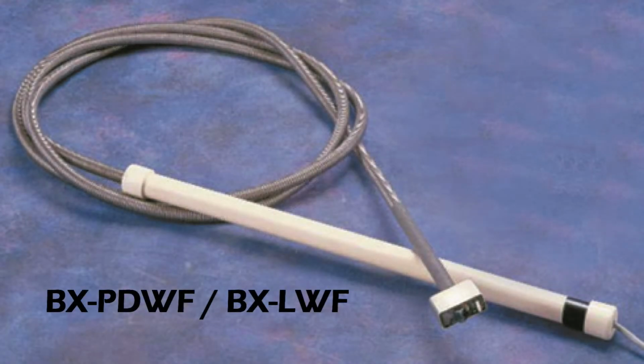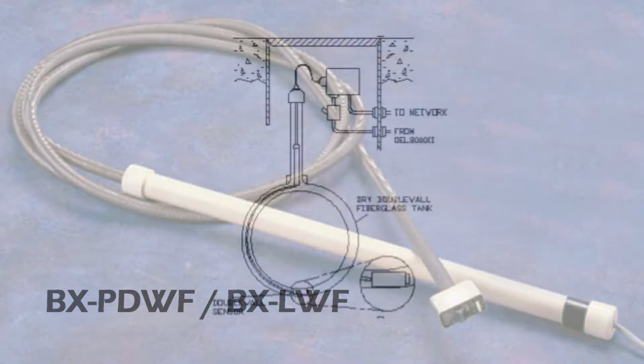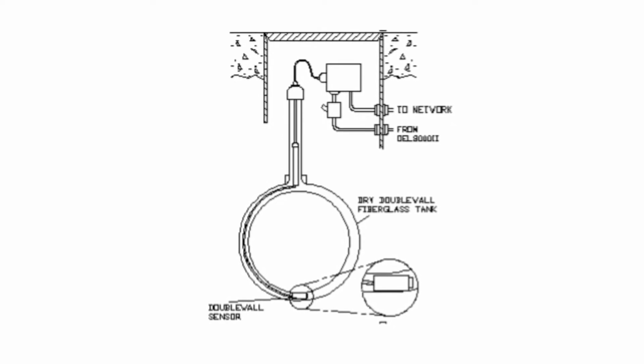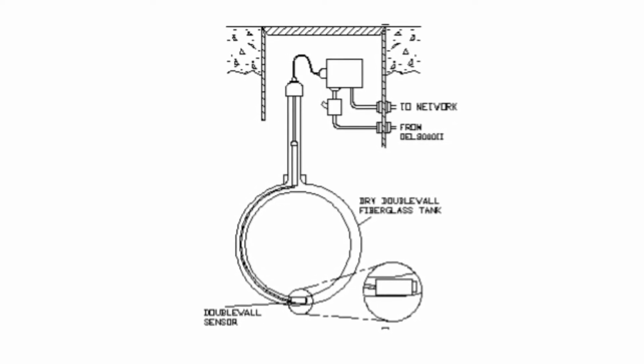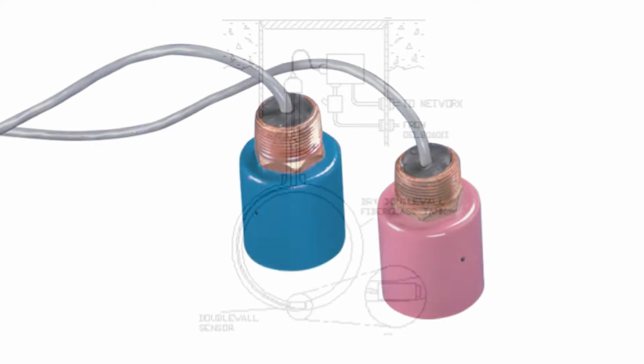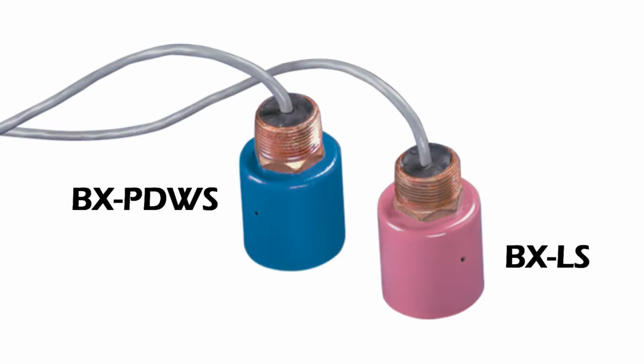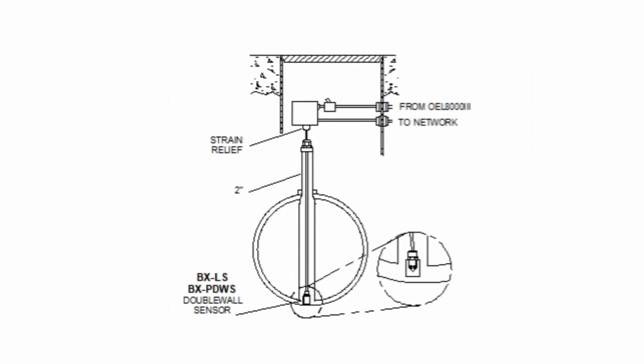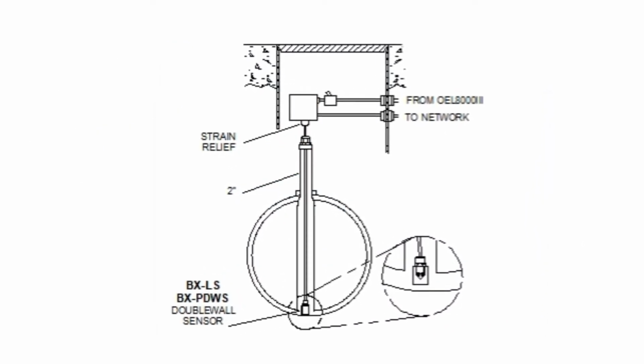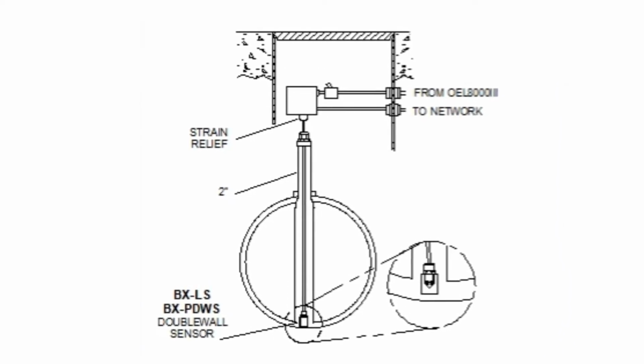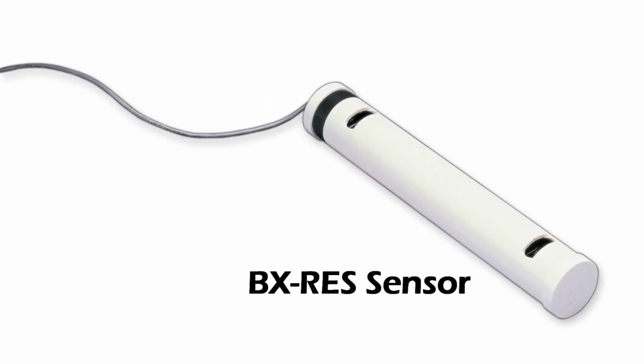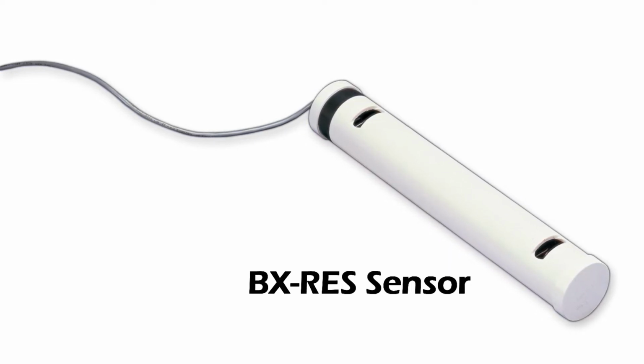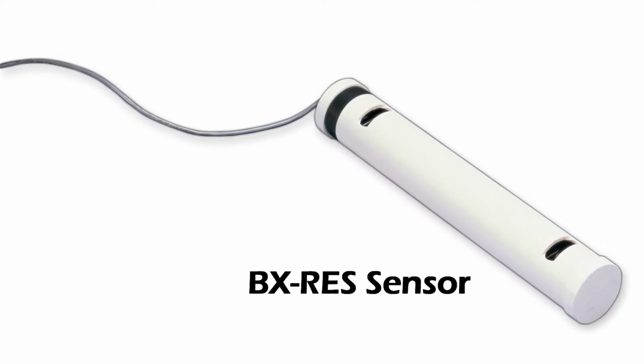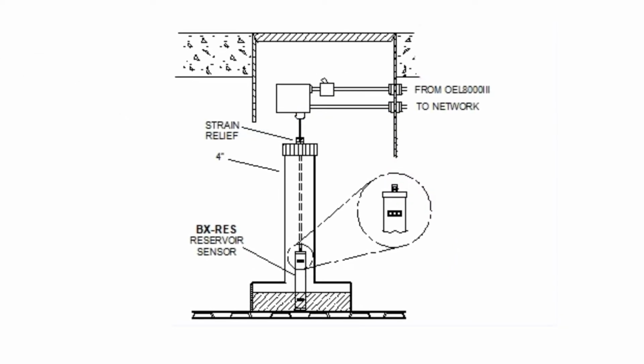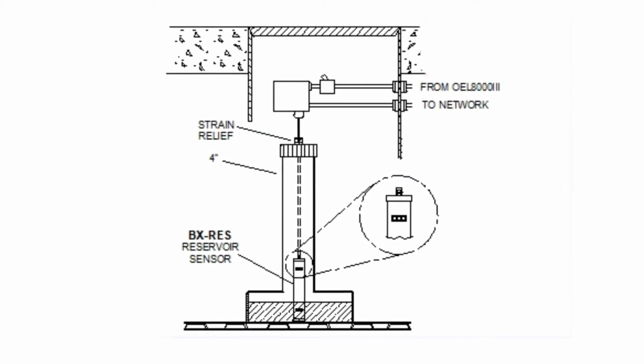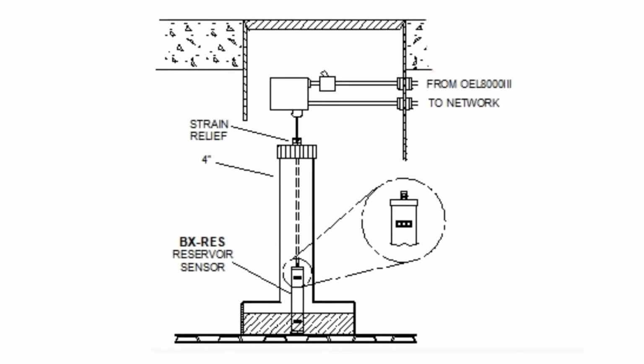The BXPDWF and BXLWF sensors are used for the annular space of a double-wall fiberglass tank and are easily installed and removed from grade. The BXPDWS and BXLS sensors are used for the interstitial space of a double-wall steel tank and are also easily installed and removed from grade. The BXRES sensor is designed for double-walled brine-filled tanks and is made of non-metallic, corrosion-resistant material. An alarm is activated to signal changes in reservoir liquid levels beyond acceptable high or low limits.